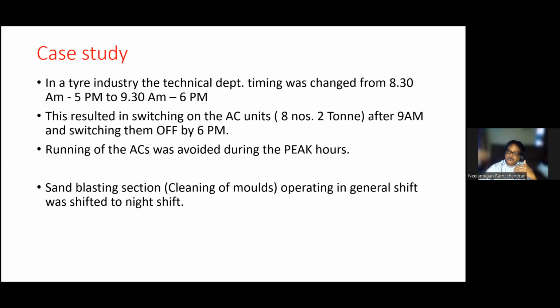the room temperature to the desired temperature. Then it will work on thermostat. So the major chunk is switched on at 8:30. So slightly the timing was changed for the development section alone, from 9:30 to 6 p.m., so that switching on the AC in the peak hour was avoided. So by simply changing the timing of things, we were able to save on 8 numbers of 2 Tonne AC. You can just calculate how much the saving would have been.